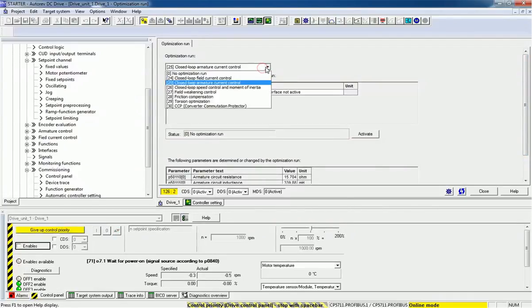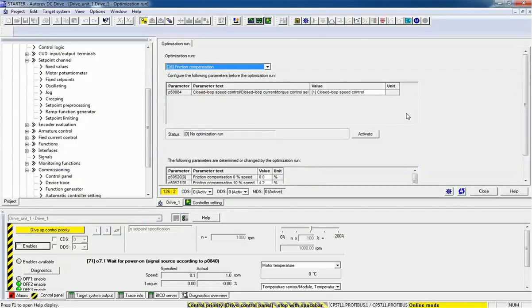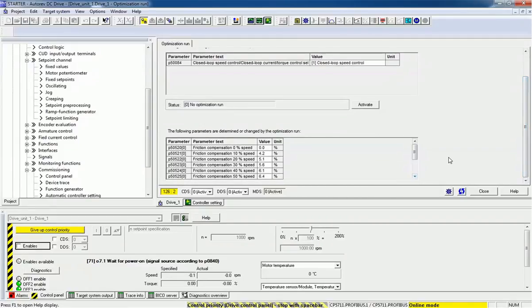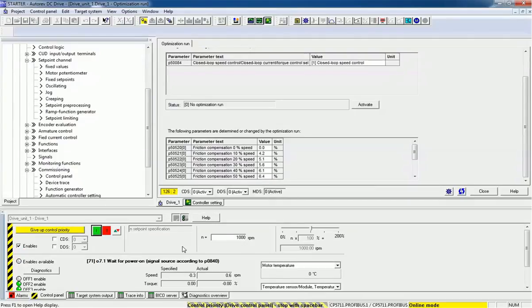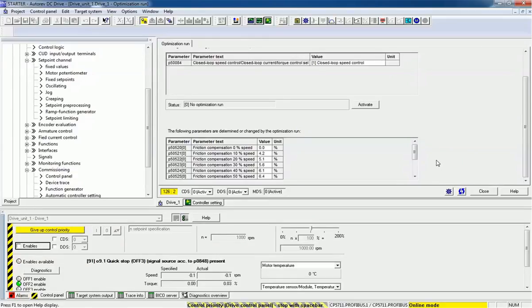Now we will check another optimization: we will go to friction compensation. From friction compensation we can know about the friction losses. For example, if we have bearings connected to the DC motor, we can calculate the mechanical losses from this friction compensation test. It will increase the motor speed step by step in percentage and after reaching 100% speed we will get the value. I will enable the motor — right now 1000 RPM is set — I will enable the drive and it will increase the motor RPM. After that we are getting the friction compensation by speed.